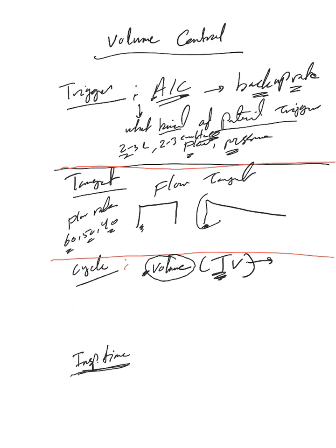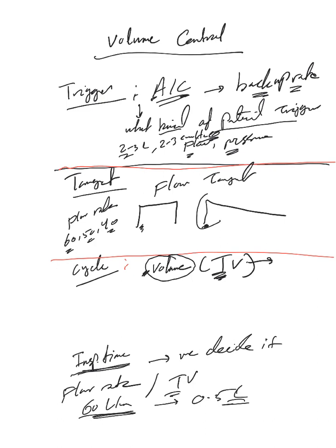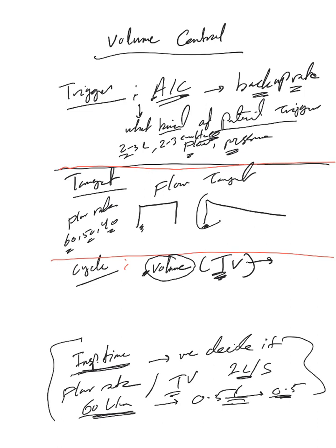That's probably what the name volume control mode came from, from the name of the cycle. Inspiratory time here is indirectly determined by us and cannot be changed by the patient breathing status. So we decided indirectly. How? We have a flow rate and we have tidal volume. So if you have 60 liters per minute and you need to deliver half a liter, which is 500 cc, just do the math. This will be one liter per second, so this will be half a second, the inspiratory time. So it's determined by us indirectly.